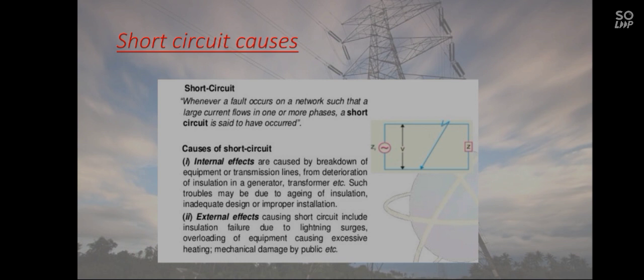Short circuit causes. Whenever a fault occurs in a network such that a large current flows in one or more phases, a short circuit fault is said to have occurred. Causes of short circuit. Internal effects are caused by breakdown of equipment or transmission lines from deterioration of insulation in a generator, transformer, etc. Such troubles may be due to aging of the insulation, inadequate design, or improper installation. External effects causing short circuit include insulation failure due to lightning surges, overloading of equipment causing excessive heating, and mechanical damage by public, etc.